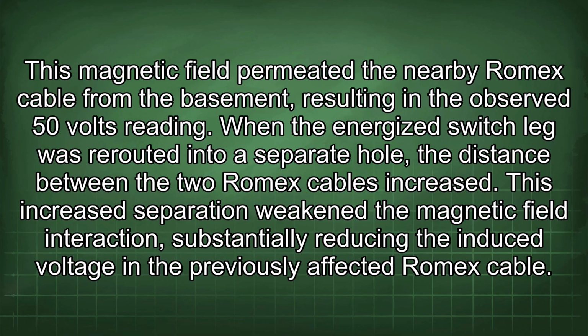When the energized switch leg was rerouted into a separate hole, the distance between the two Romex cables increased. This increased separation weakened the magnetic field interaction, substantially reducing the induced voltage in the previously affected Romex cable.